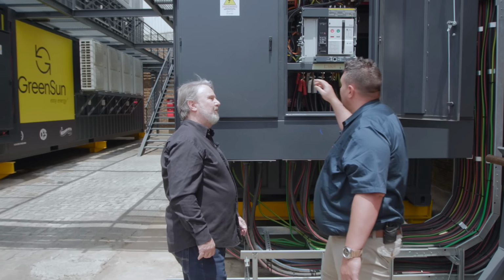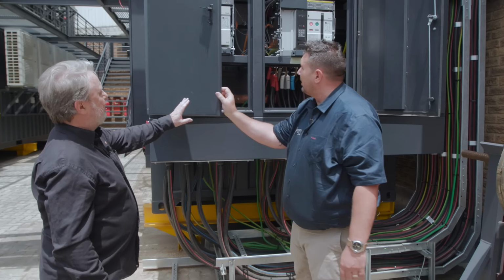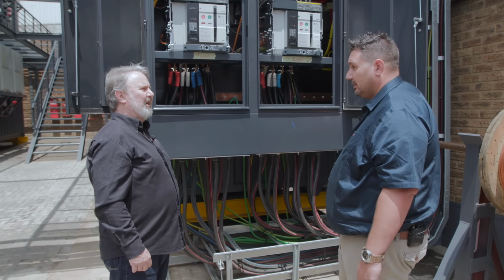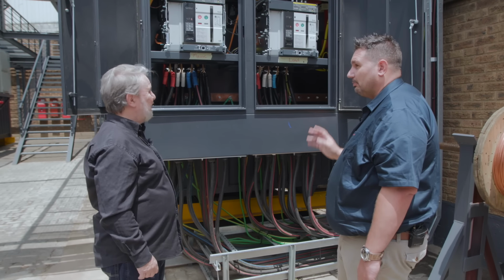Inside here, we have 2 by 2000 amp ACBs that basically take care of the changeover once Sigenergy senses that there's a grid outage coming. How many amps are you switching here? 2000 amps, times 2.